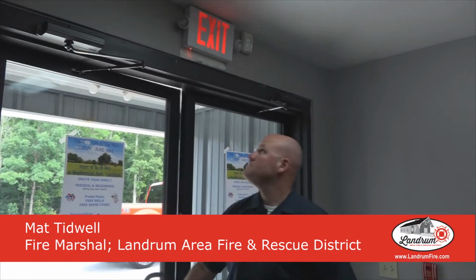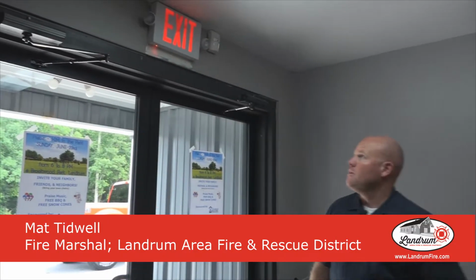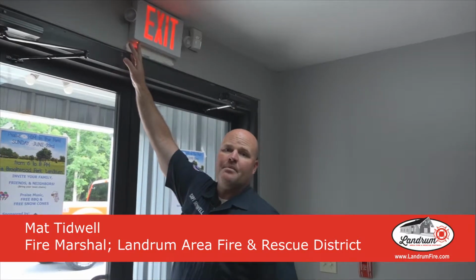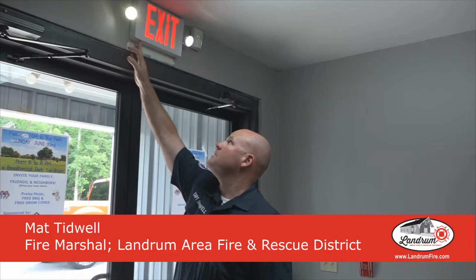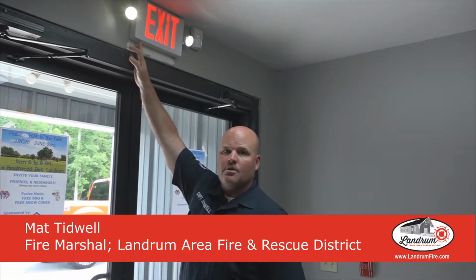Closes good. Above my head is an exit sign. It is illuminated. The only thing I will check, if the power does go out, we're looking for 90 minutes of illumination with no power, so it's a battery backup. And you notice that the lights kick on and the exit light stays illuminated red. So we get another check here.